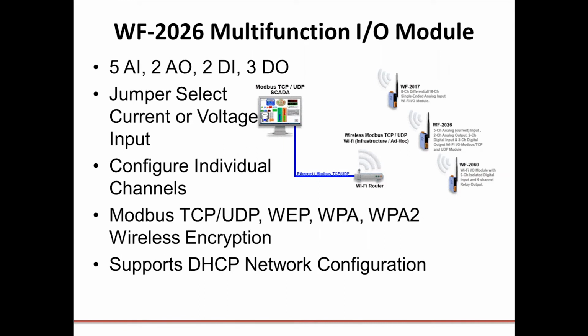That's a jumper select to change between current or voltage on both the input and output. This one also supports Modbus TCP and Modbus UDP, along with individual channel configuration via the jumper select on your analog input and output channels. It also supports WEP, WPA, and WPA2 wireless encryption, supports DHCP network configuration, and provides overload and short circuit protection on its digital outputs, as well as plus or minus 4 kilovolt contact ESD protection.